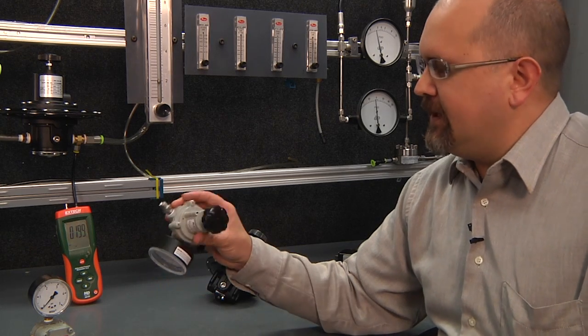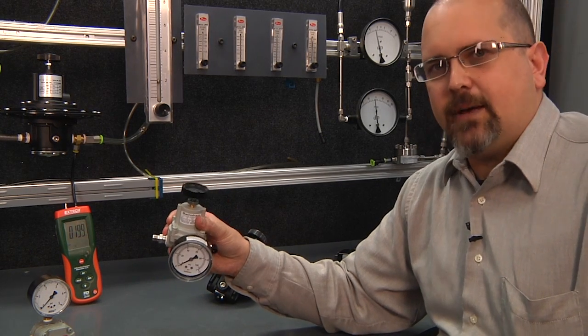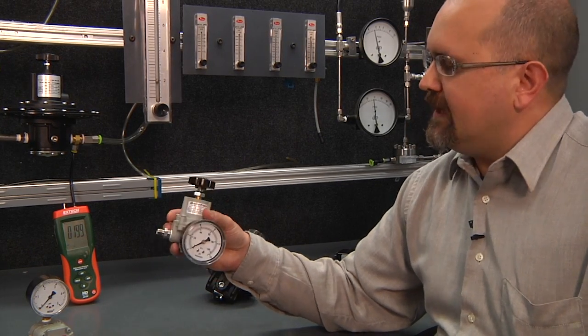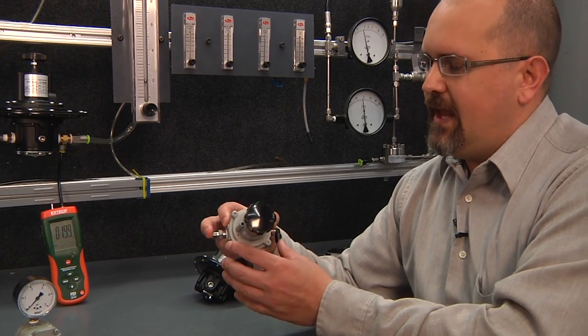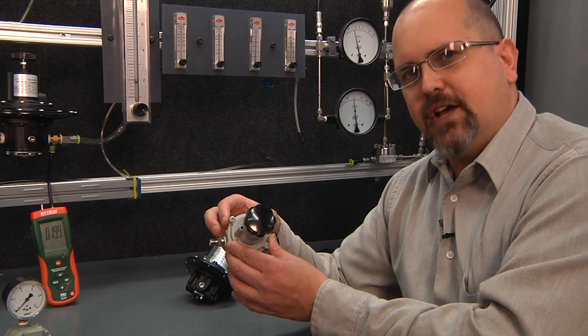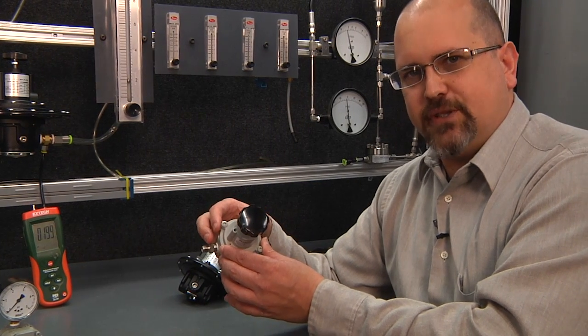The problem with using a standard regulator in an application like that is that the diaphragm sense area is just simply too small. The diaphragm is not large enough to effectively sense the pressure being controlled.